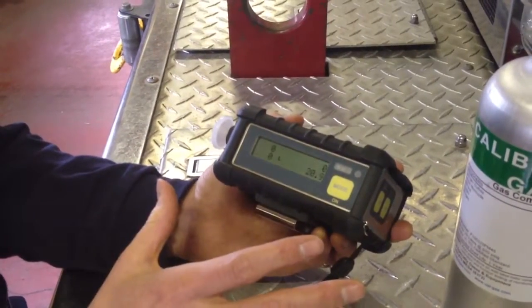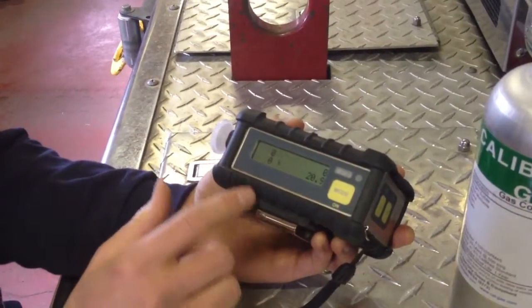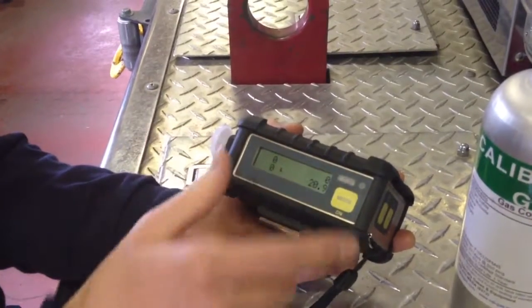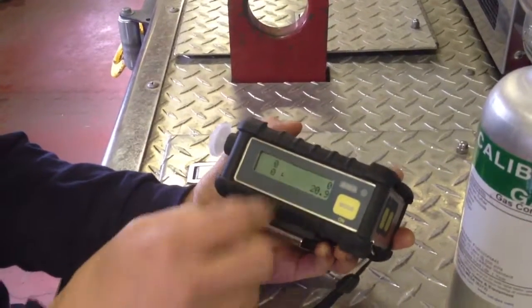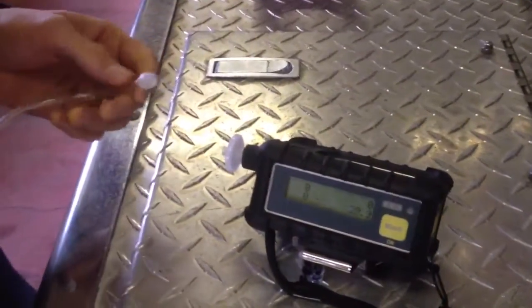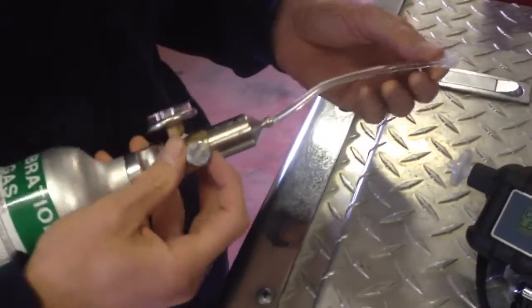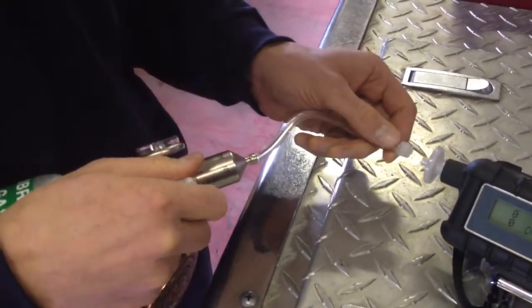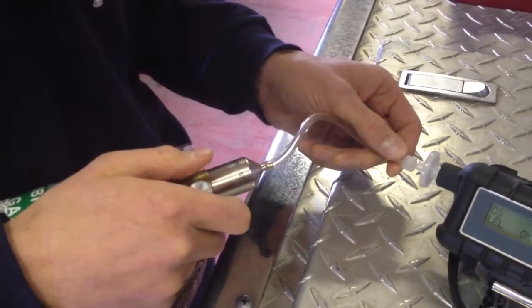Once we've accomplished our 0 calibration and all of our sensors read 0 or 20.9, we're going to apply our gas. We set that down there, and you always want to turn your gas on before you apply it. So I'm just going to turn it on, hear a little bit coming out, and then stick it on there.